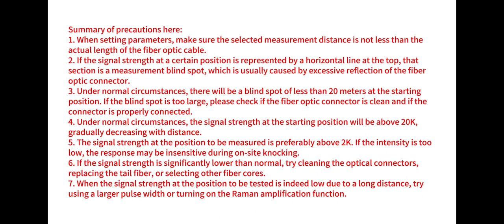6. If the signal strength is significantly lower than normal, try cleaning the optical connectors, replacing the tail fiber, or selecting other fiber cores. 7. When the signal strength at the position to be tested is indeed low due to a long distance, try using a larger pulse width or turning on the Raman amplification function.